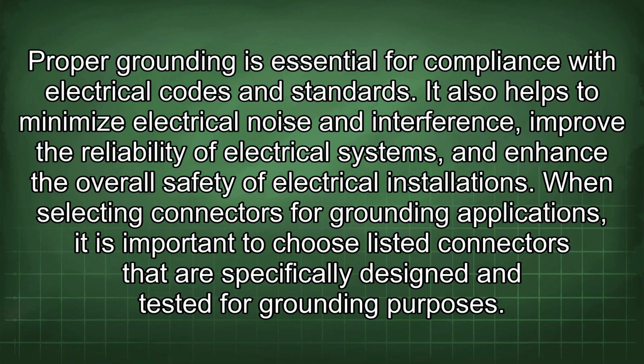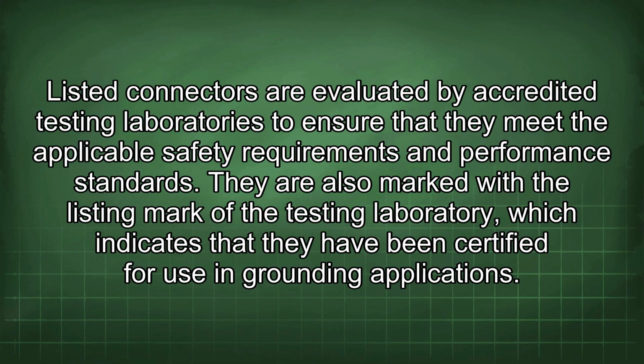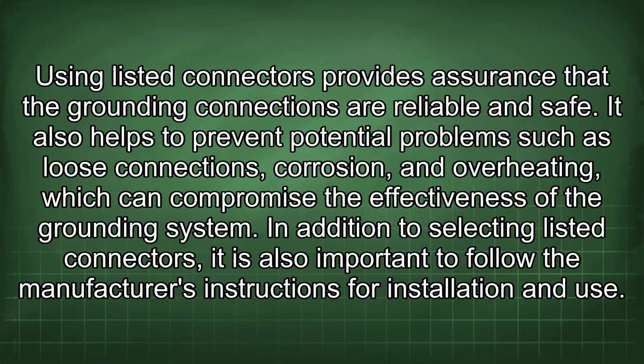It also helps to minimize electrical noise and interference, improve the reliability of electrical systems, and enhance the overall safety of electrical installations. When selecting connectors for grounding applications, it is important to choose listed connectors that are specifically designed and tested for grounding purposes. Listed connectors are evaluated by accredited testing laboratories to ensure that they meet the applicable safety requirements and performance standards. They are also marked with the listing mark of the testing laboratory, which indicates that they have been certified for use in grounding applications. Using listed connectors provides assurance that the grounding connections are reliable and safe. It also helps to prevent potential problems such as loose connections, corrosion, and overheating, which can compromise the effectiveness of the grounding system.